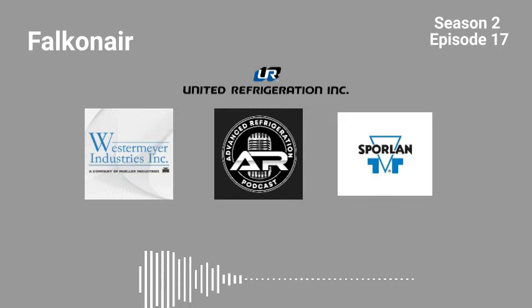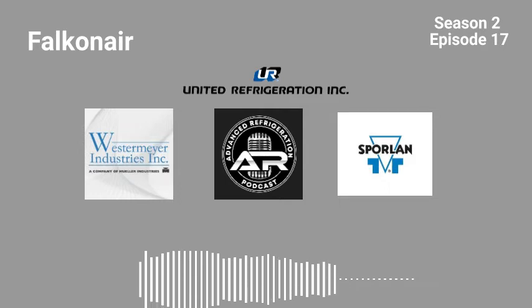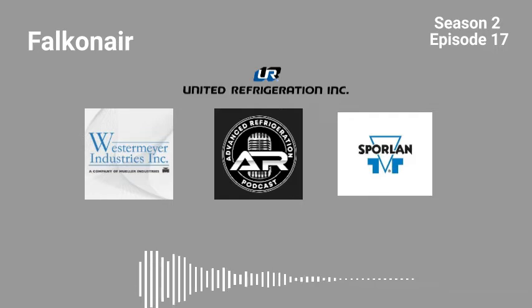If they're going to implement, go ahead, Kevin. Sorry, I have a question. So I'm very interested in something with this. We have a lot of dehumidification issues on older stores where they have no reheat, where the reheat's been cut out, running rack stores. They're doing these glass door conversions, and the store AC has not got much loving, to be honest. It's been neglected. It's not needed to run most of the time, and the cooling was done through the cases. Well, now they close up the cases, and now we have all these dehumidification issues.